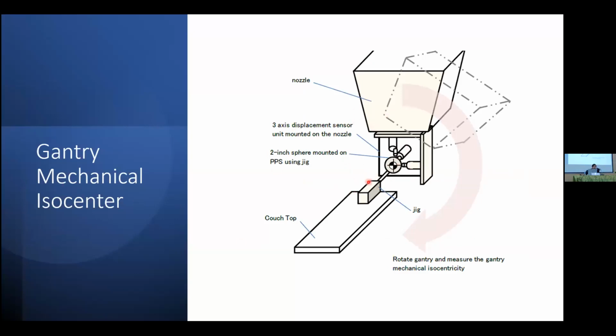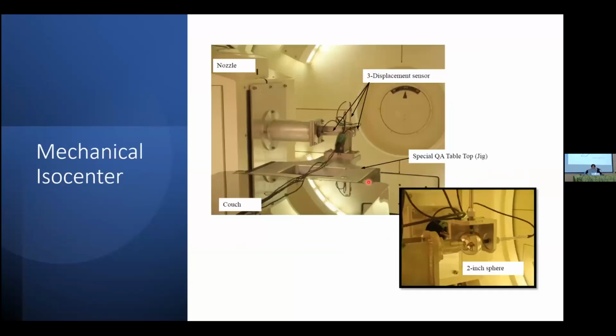The gantry isocenter mechanical. Again, this is one of the things, and it's probably better doing it this way. As a clinic, you should not buy this thing, right? Because you're going to use it one time during acceptance and technical commissioning. And then you're going to do other tests, but this is the high precision test. So this is something the vendor should have, and you use their tool when you're doing it. On the flip side, the vendor is probably not going to bring their water tank to do the measurements. So they'll probably use your water tank to do some of those measurements. So just discuss with the vendor.